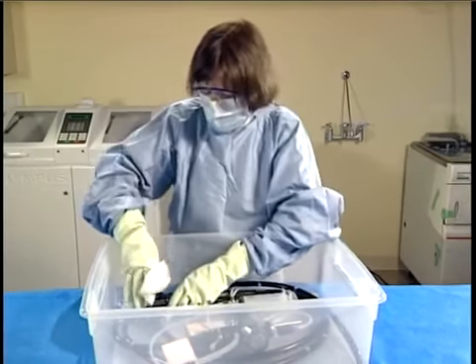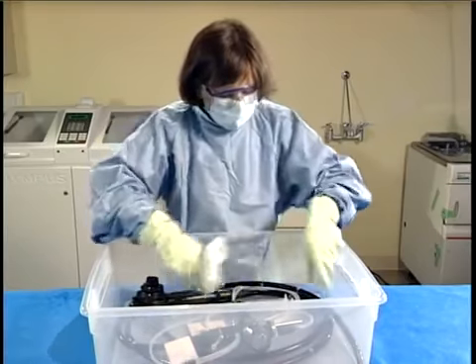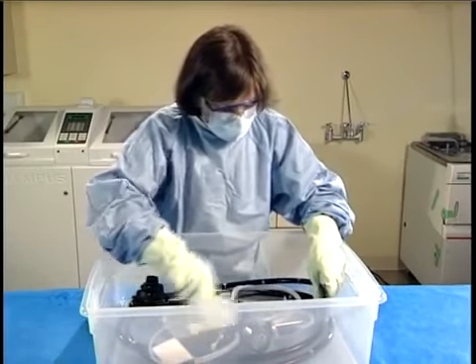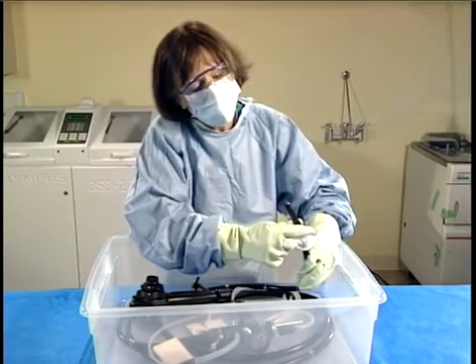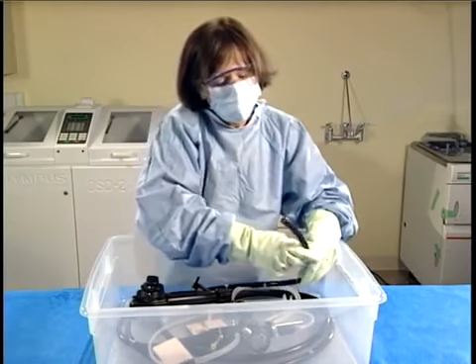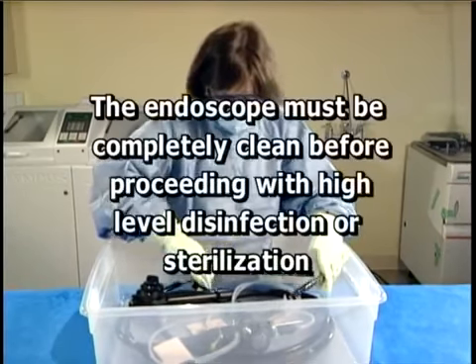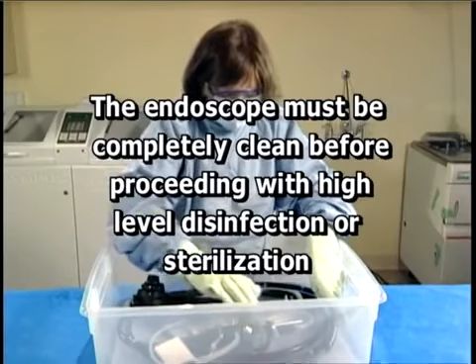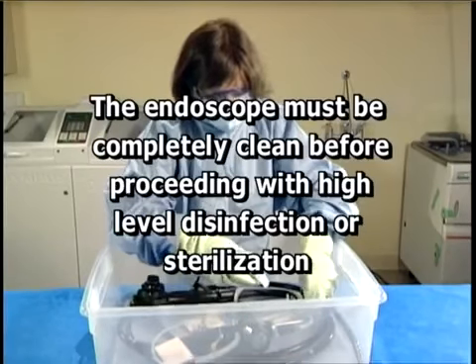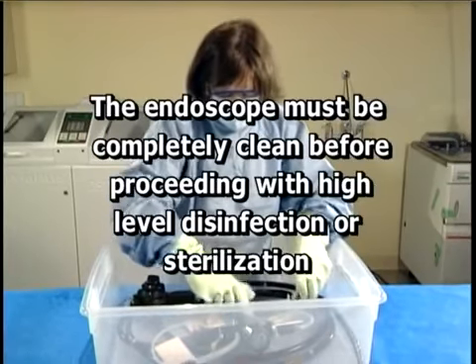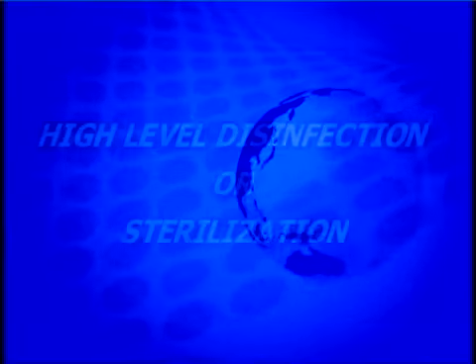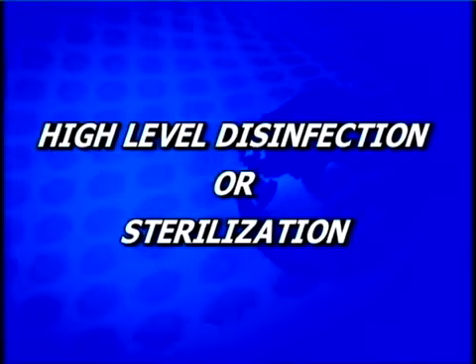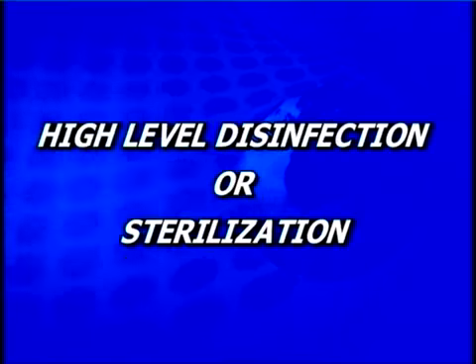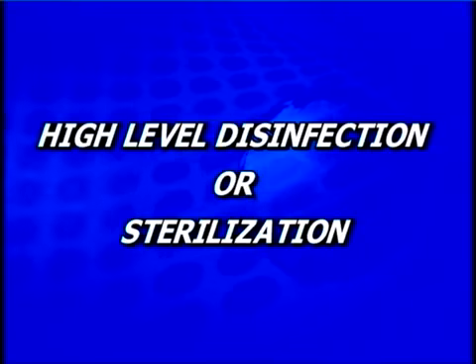Visually inspect the endoscope and cleaning accessories. If any debris remains, the manual cleaning process must be repeated. The endoscope must be completely clean before proceeding with high-level disinfection or sterilization. The next step in reprocessing the endoscope is either high-level disinfection or sterilization.